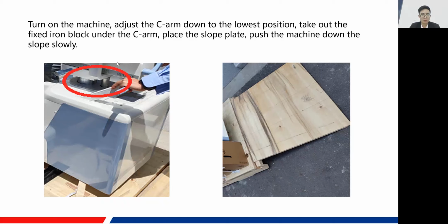Of course, we have turned it on before, and we adjust the arm down to the lowest position in order to take it out, right? Of course, don't forget the slope plate. This is for your safety when taking the C-arm out from the plate. And pay attention to the C-arm because it's very heavy, and you need to push the machine very slowly and carefully.